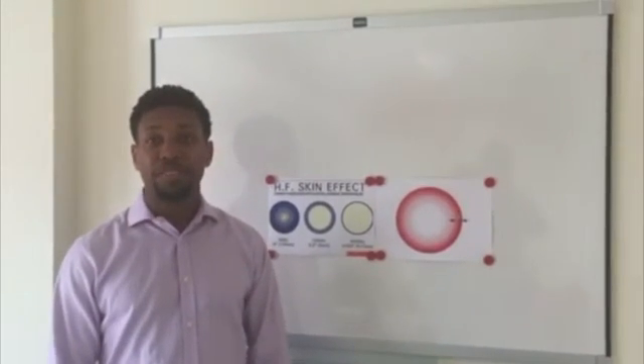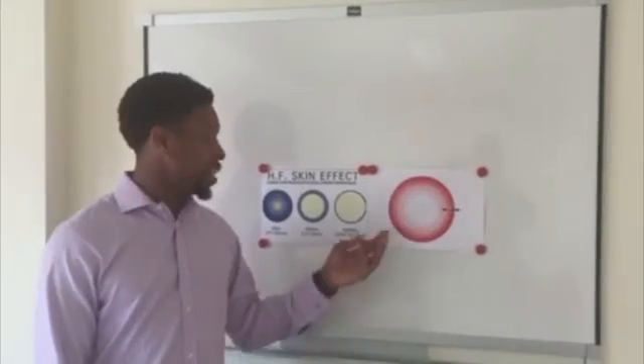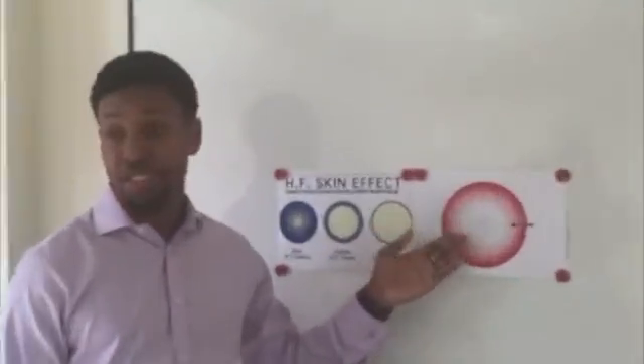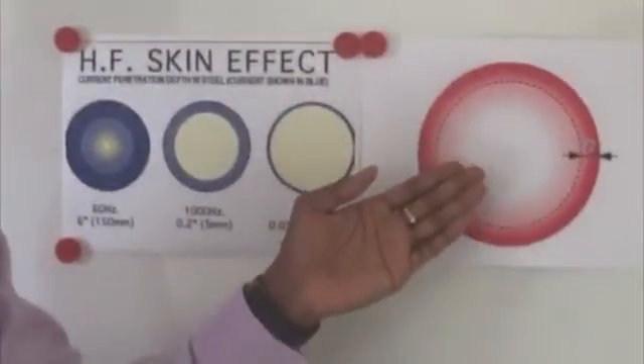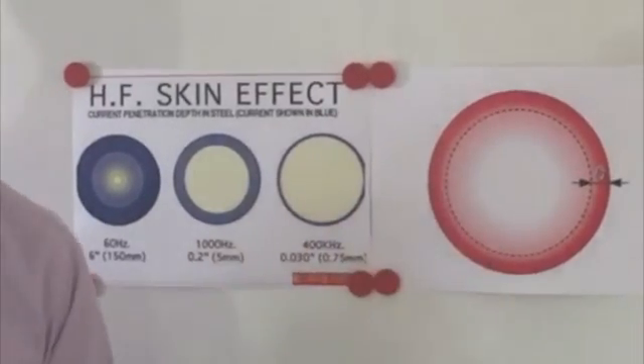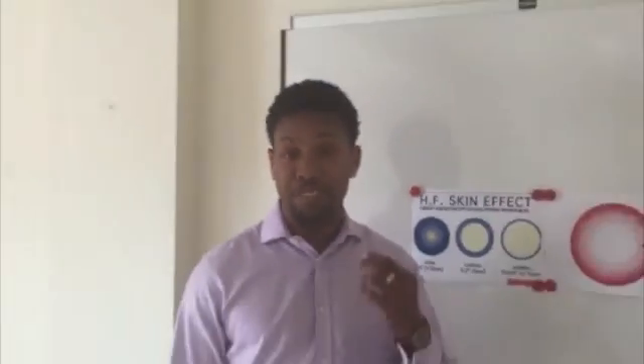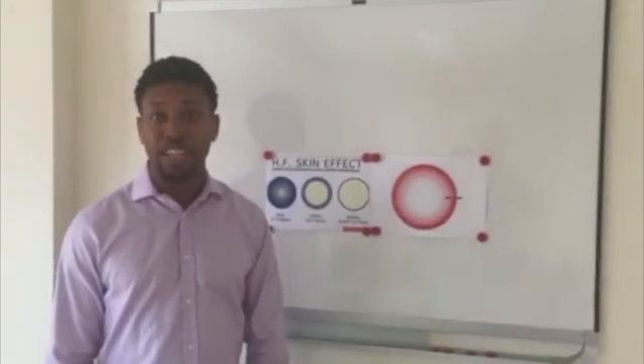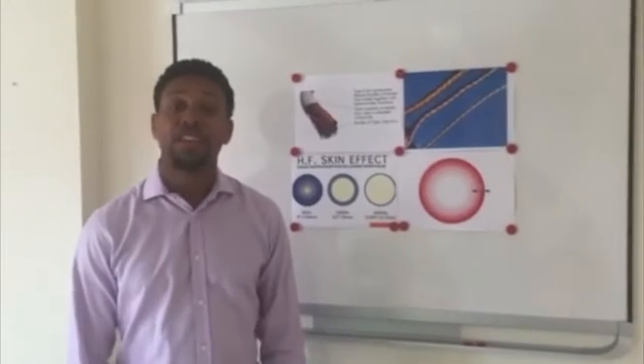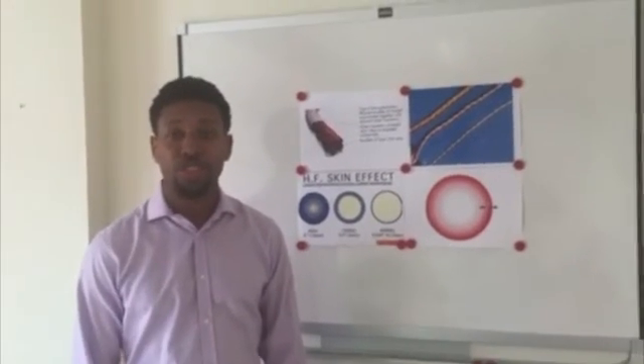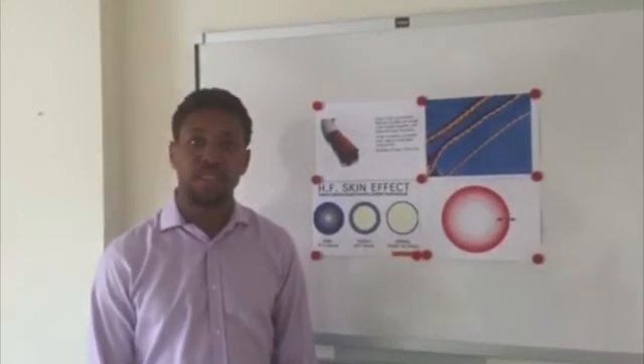The problem with the skin effect is it leads to a lot of wasted material within the cross-section. There's no current flowing through the center, and so there's a lot of extra weight you have in your cross-section which isn't actually being used. A further issue is the effective resistance of your overhead line is increased. There are several methods we can use to reduce the effects of the skin effect.